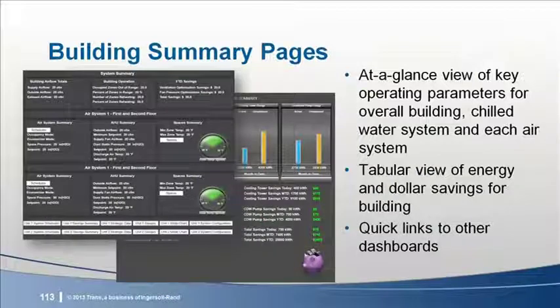A facility manager would like to know that the whole building is operating properly. As such, a dashboard that brings together relevant operating metrics for the air systems as well as the chilled water system rolled up into whole building performance is valuable. From a chiller plant perspective, it should point out things in the building that might affect plant performance, such as each air system's chilled water delta T. Pointing out an air handler that is causing low delta T as soon as possible allows the facility manager to address it before it becomes systemic. The phrase "follow the money" comes to mind.